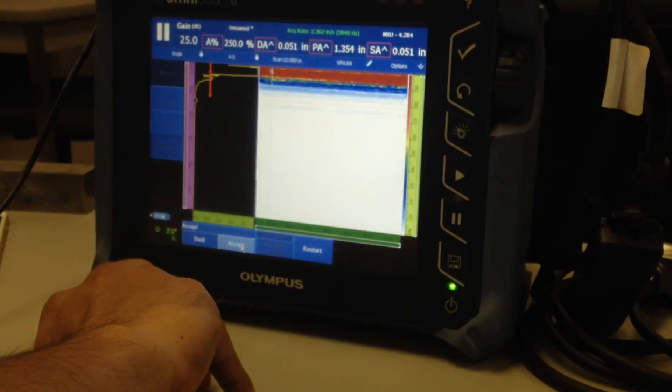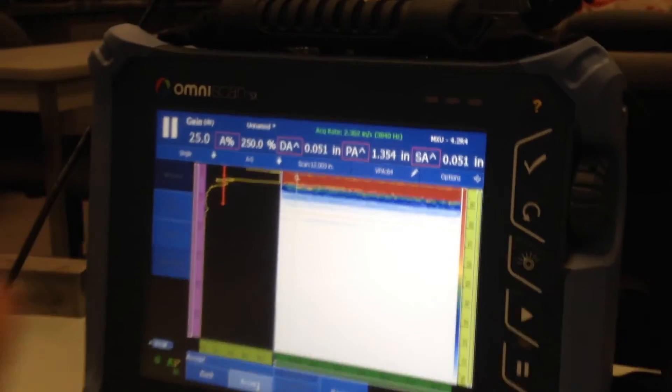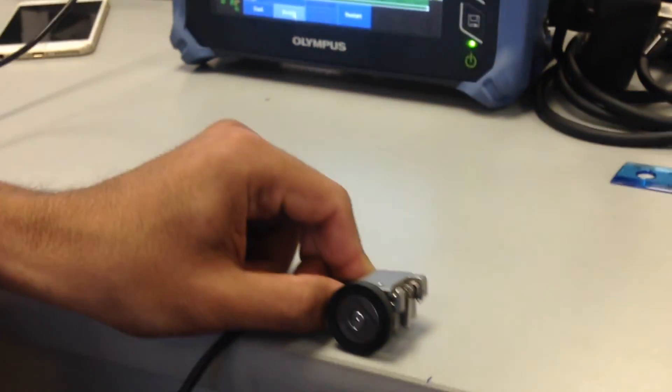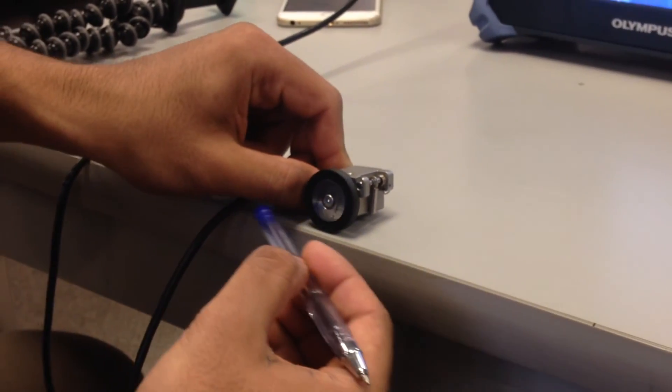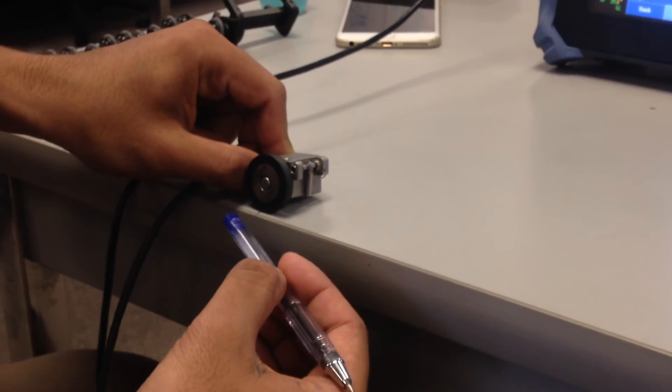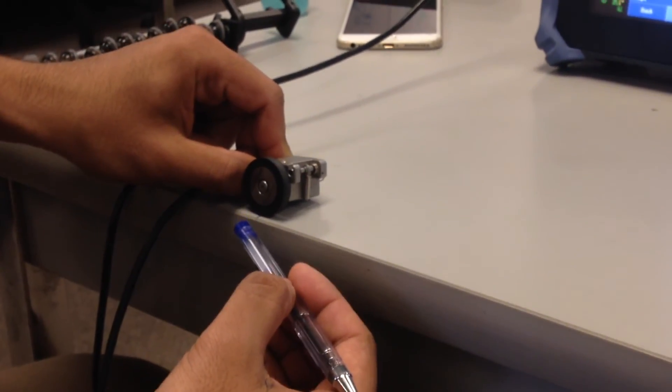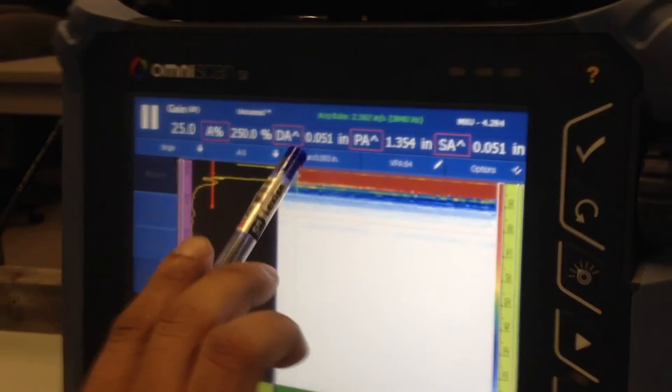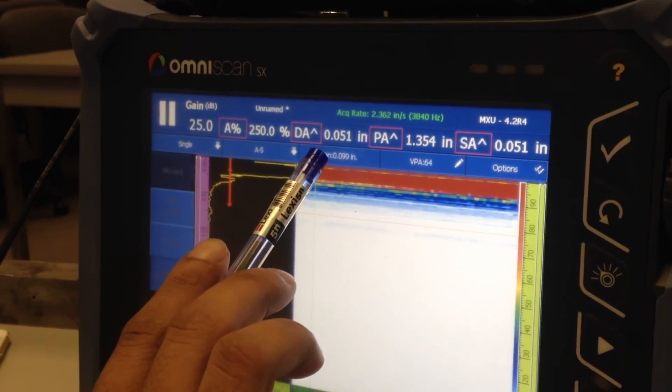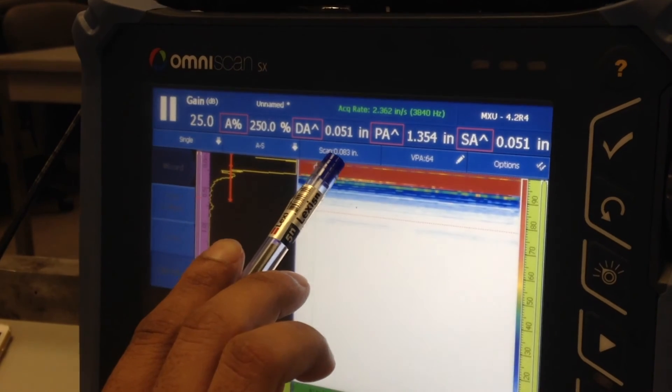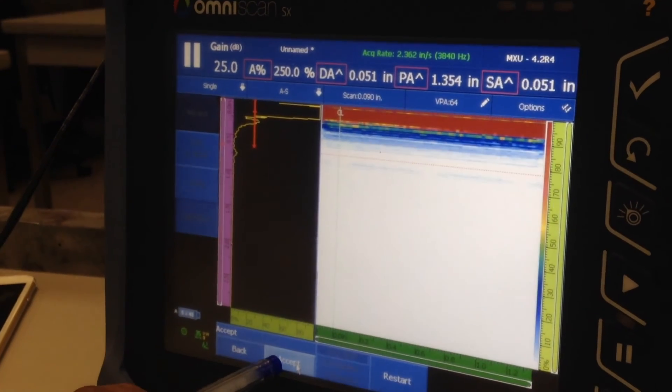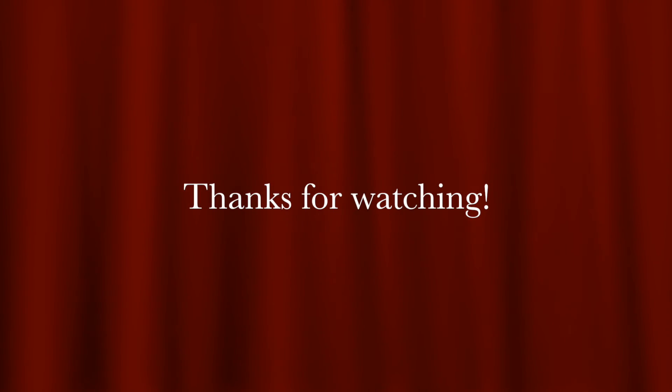So now the scan reads 12. I'm going to go all the way back to zero without watching the screen, making sure I'm dragging it in a straight line. And once I reach zero, I'm going to make sure that my scan reaches zero. So right now it is 0.00808. That's acceptable. I'm going to click accept this next one.